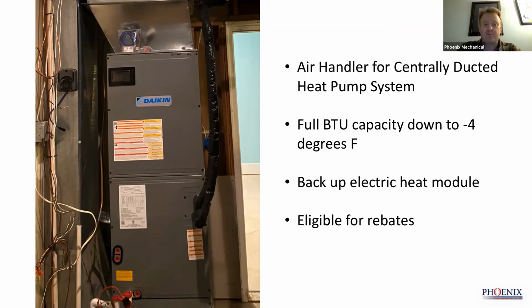This can be your primary heating system. We would evaluate your house to make sure there's enough coverage with the existing ductwork to adequately heat it. If it's already your heating system, a ducted system, it should transition nicely, and that's something we evaluate. Most homes are compatible with this type of system. If it's your sole source of heat, a backup electric could be put in as an emergency backup in case there's ever a problem with the heat pumps. But we try to size it so the heat pump will handle all of your heating needs.